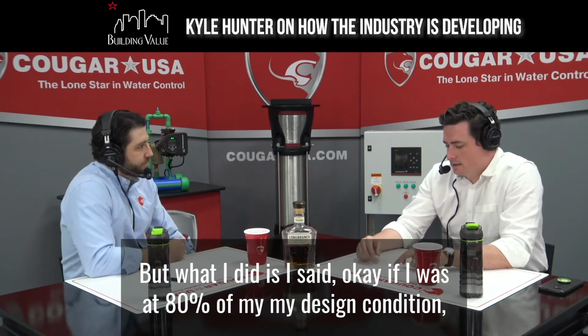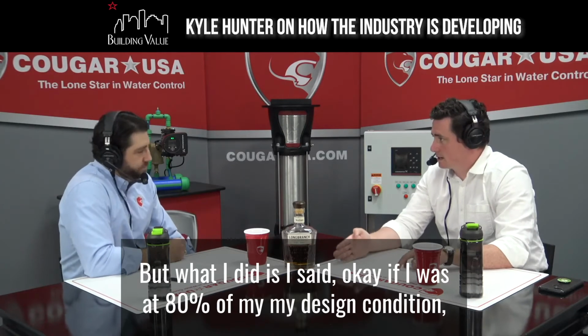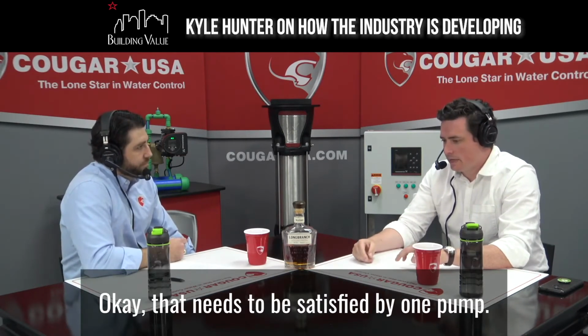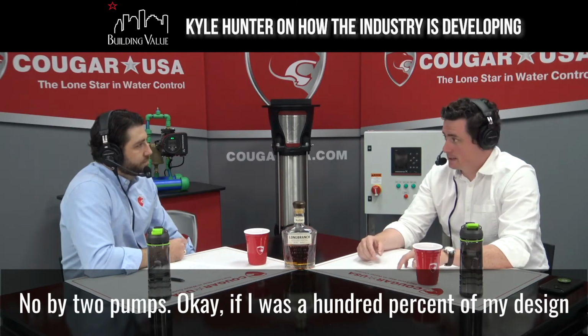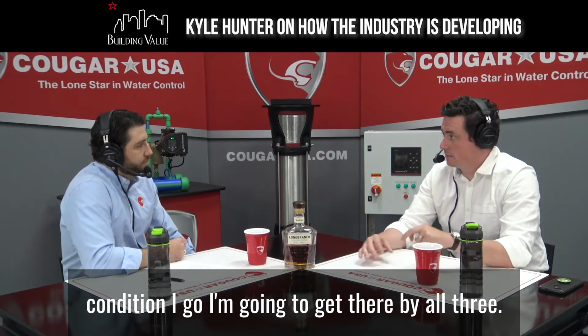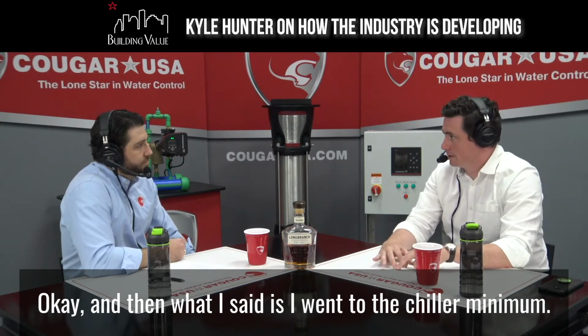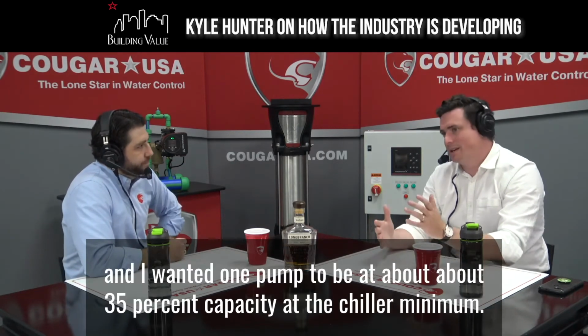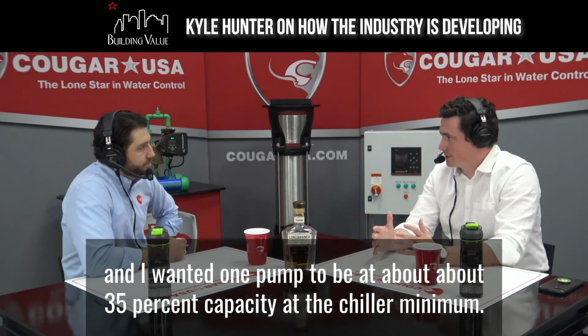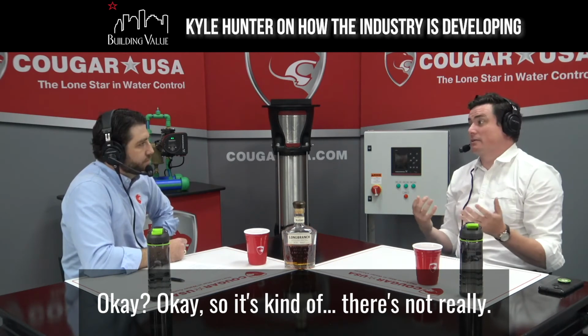What I did is I said, okay, if I was at 80% of my design condition, that needs to be satisfied by one pump. Okay, no, by two pumps. If I was at 100% of my design condition, I'm going to get there by all three. And then I went to the chiller minimum, and I wanted one pump to be at about 35% capacity at the chiller minimum. So there's not really redundancy there.